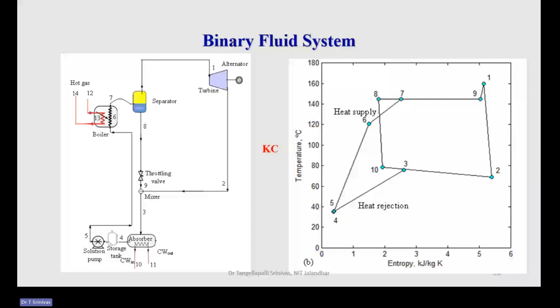It is a reversed vapor absorption refrigeration system. So the merit of using this binary fluid system is that we can design a system so that simultaneously we can get cooling, like a vapor absorption refrigeration system, and also electricity, like a Kalina cycle system. This layout is designed only for power generation. This layout we can slightly modify into cogeneration, and if it is extended to cooling, that plant layout is called a cooling cogeneration system. So the cooling cogeneration system gives electricity as well as cooling, that means the output of the cooling evaporator. This is such a cooling cogeneration system.